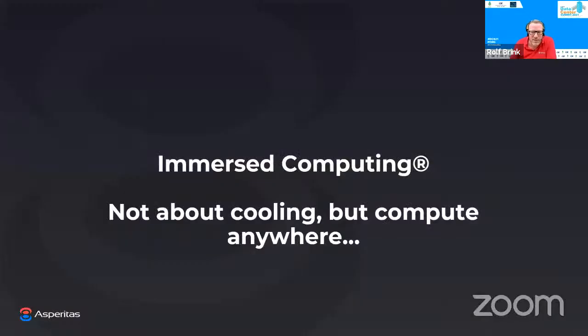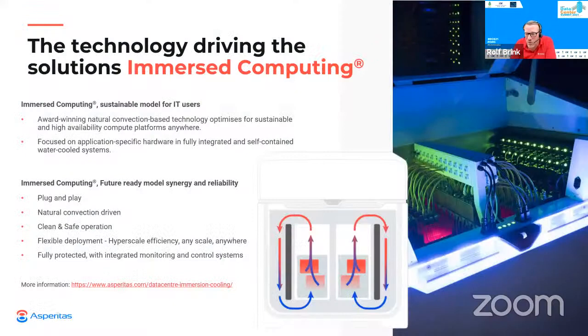So I guess it's time to explain what it is that Asperitas does exactly. We're an immersion cooling provider, and immersion cooling is literally submerging IT equipment in a dielectric fluid, dielectric because it cannot conduct electricity. The main element which makes Asperitas unique is that we can circulate dielectric fluid without any pumps. Our system contains no moving parts at all, and is completely passive in nature.